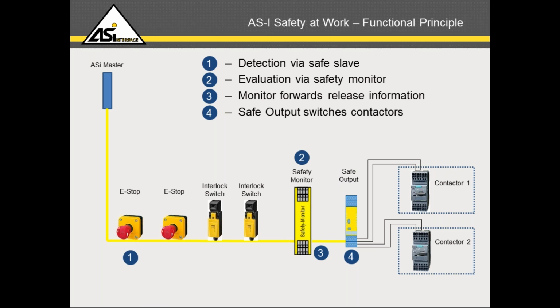Now that's greatly simplified, but to summarize, all safe slaves operate via a 32-bit code sequence. Safe inputs can detect an unsafe condition and change their 32-bit response, which is monitored by the safety monitor. The safety monitor compares expected versus received values, and if there's a delta, it forwards a control decision based on what you've programmed it to do, and the output device then safely shuts down the appropriate circuit.